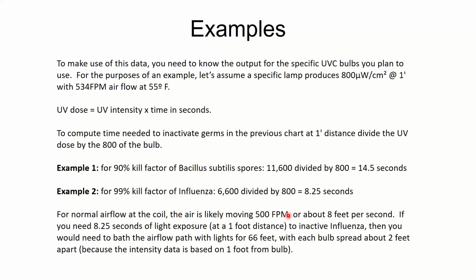Well, at 500 feet per minute, I'm only going to get 8.25 seconds within the 1 foot distance. So I'm not going to get enough to kill it all. Am I going to kill a little bit of it? Sure, because some of it's going to be closer than 1 foot. Some of the germs are going to come by only an inch away from the bulb instead of a foot, and the intensity will be higher. But for all the germs that are 1 foot away, I need 14.5 seconds. Now the duct's pretty big. I may be 3 feet away from the bulb. Now I need like 50 seconds or something ridiculous like that.